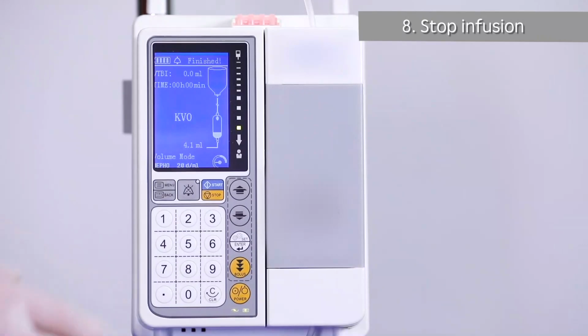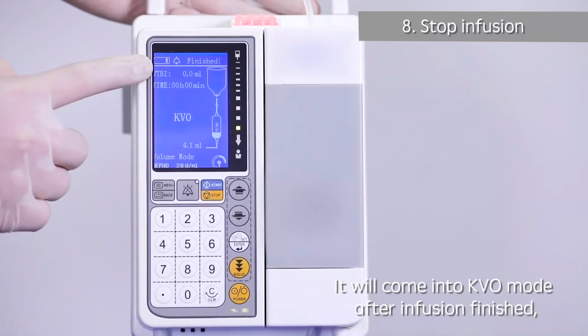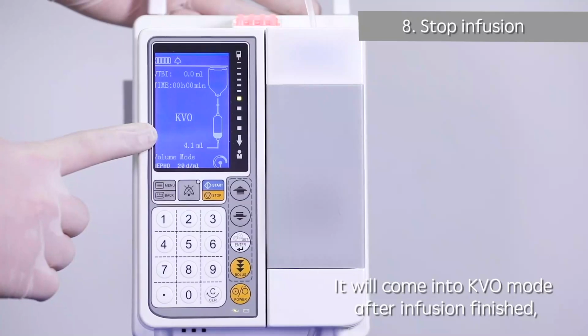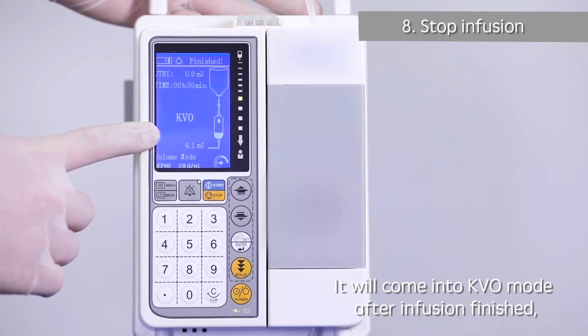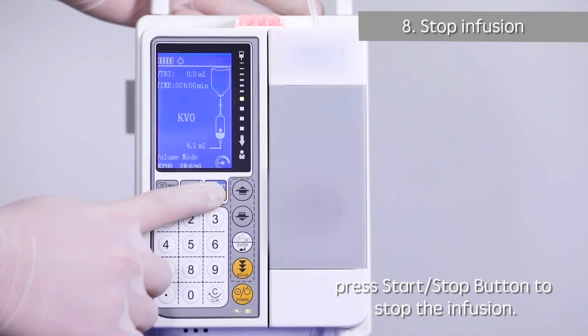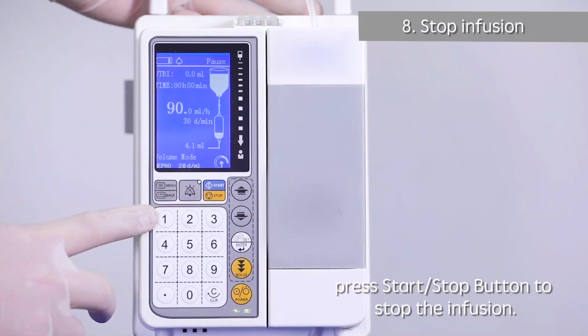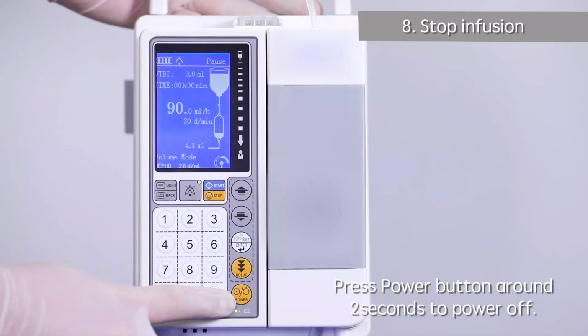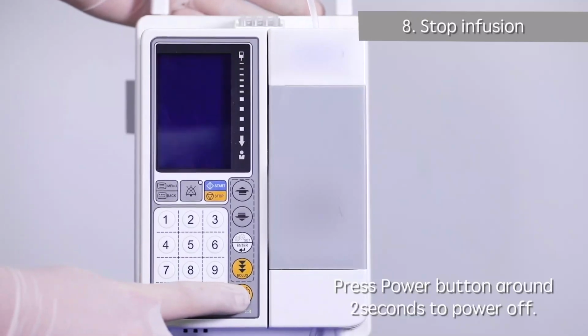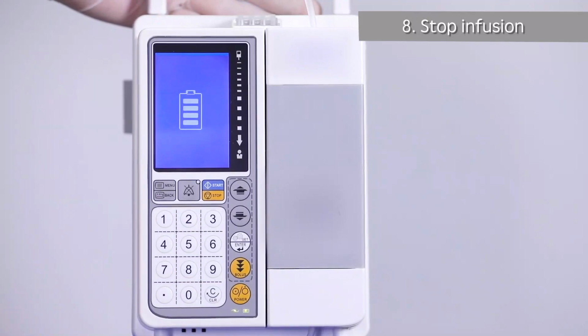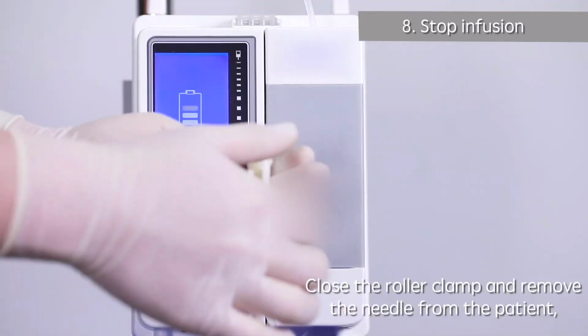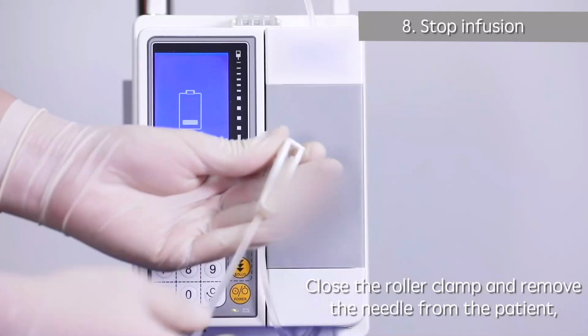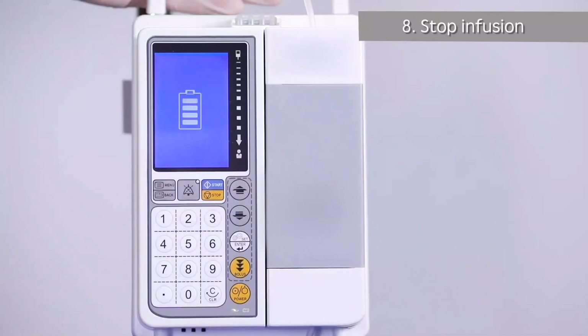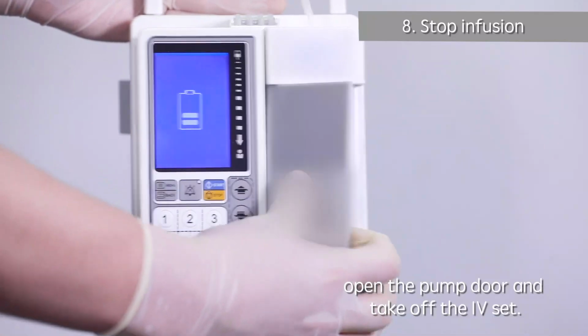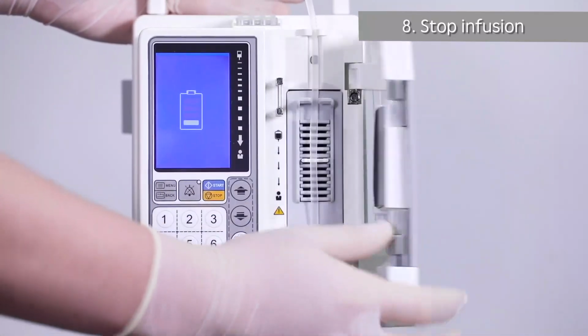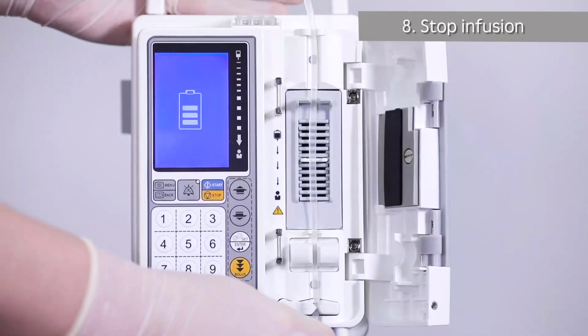8. Stop infusion. It will come into KVO mode after infusion finished. Press Start/Stop button to stop the infusion. Press the Power button around 2 seconds to power off. Close the roller clamp and remove the needle from the patient. Open the pump door and take off the IV set.